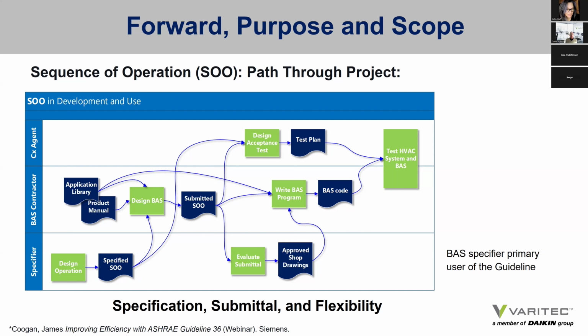The BAS specifier will be the primary user of the guideline, and he has to come up with an actual product, a sequence of operation that is to be given not only to the controls contractor, but also to the commissioning agent. Then the controls contractor takes the project sequence and brings their own wisdom and experience in evaluating those sequences, and has some margin of flexibility to influence that sequence, which is then submitted for reevaluation by the engineer. And that engineer evaluates the submittal document and lists any objections, approvals, edits or markups before that document is approved and given back to the controls contractor to write into code and put into the actual controllers within a building design.